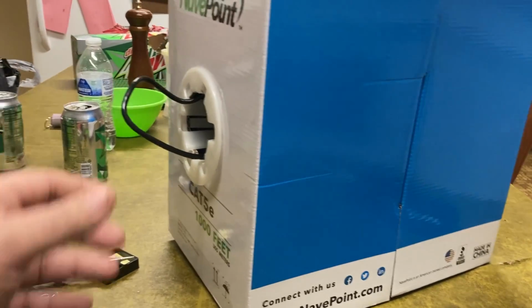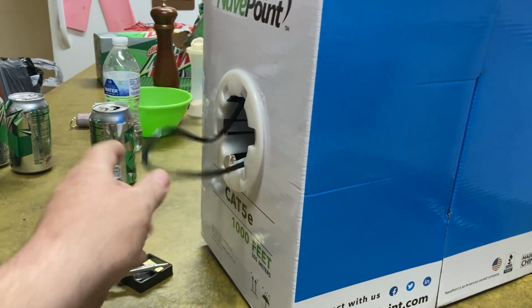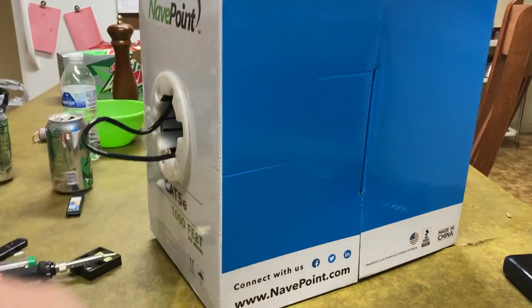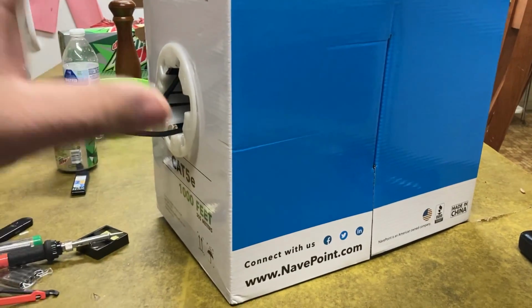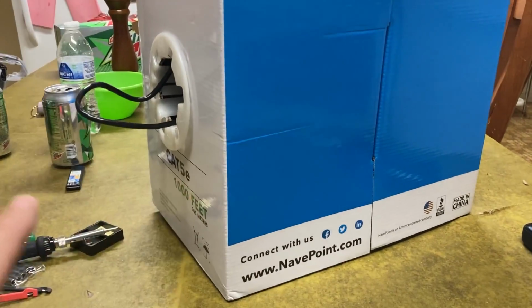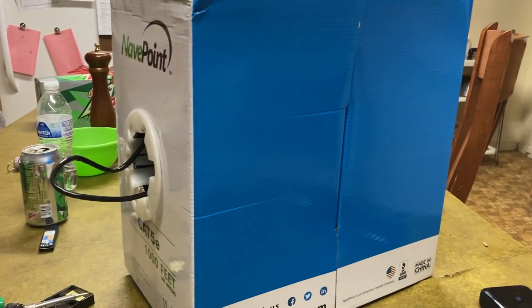In a closed plenum system, though, you don't have to worry about that. You can use this cable because as the air circulates back, it's pulling it through the ductwork directly from the room, no matter what's burning up in the ceiling.